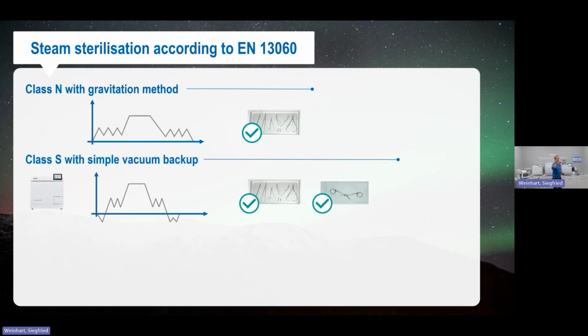You've then got S-class, which stands for specific. It's specific to the manufacturers, but the vast majority of S-classes will normally incorporate 1 or 2 vacuum pulses in there. So by the nature of incorporating 1 or 2 vacuum pulses through the use of a vacuum pump, it automatically opens up the S-class to a wider range of load types.